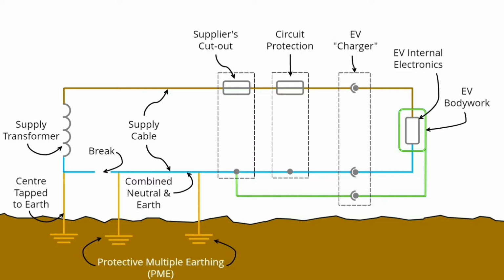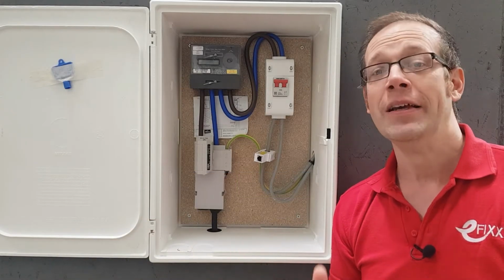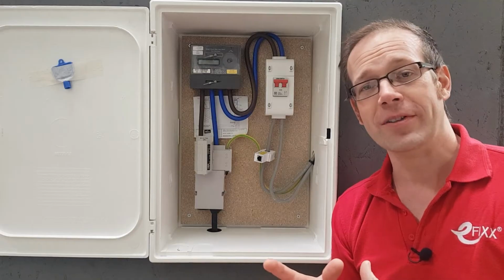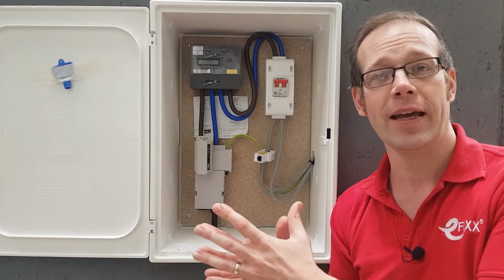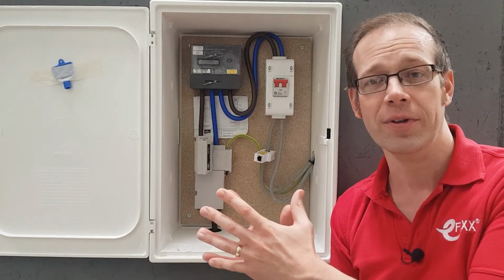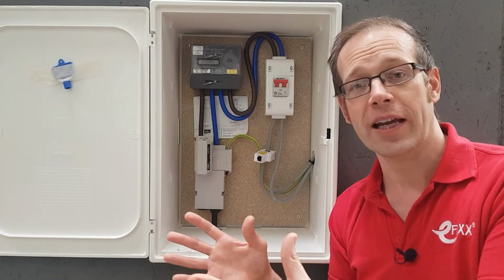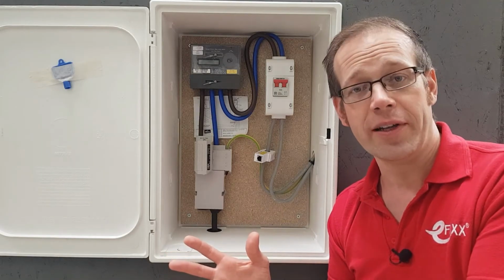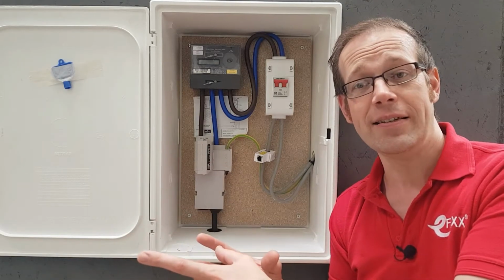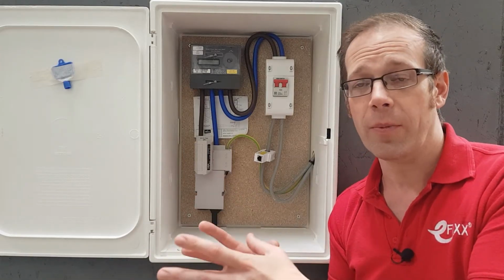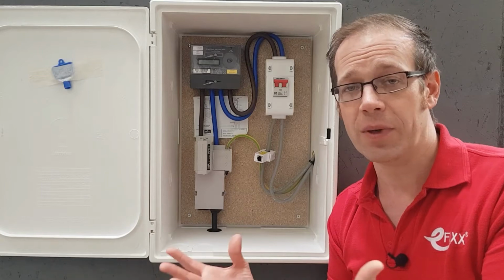Another precaution is that along the length of the supply cable, the combined neutral and earth is physically connected to the literal earth that we walk around on via electrodes, or rods as we call them, along its length. This precaution is what's called protective multiple earthing, or PME. But what has this got to do with EV charging? Well, one issue is that the only place that one of these PME rods is actually installed and connected is where the supply cable to a property comes off the main cable in the road. They're not really installed along the length of the standalone cable to your property. So if the combined neutral and earth connection in the torpedo joint in the road becomes disconnected, and this does happen sometimes, then we've got a big problem as all the exposed conductive parts of the installation become live.